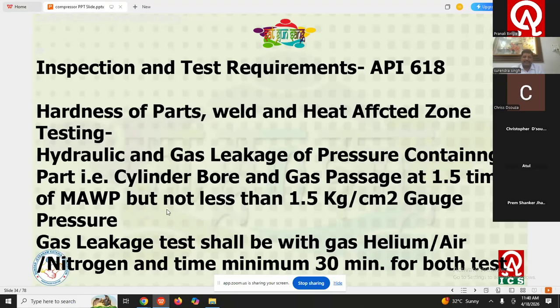So this is one reference criterion given in API 618, that the hydraulic pressure must be 1.5 times the maximum allowable working pressure. So if my maximum allowable working pressure is, suppose, 40 kg per centimeter square, then my hydraulic pressure shall be 1.5 times 40, that is 60 kg per centimeter square. But in no case shall it be less than 1.5 kg per centimeter square.